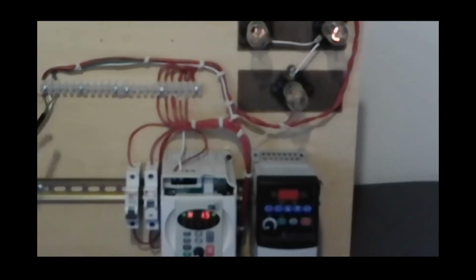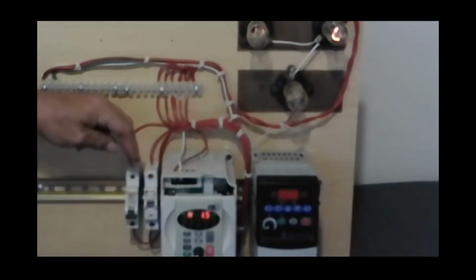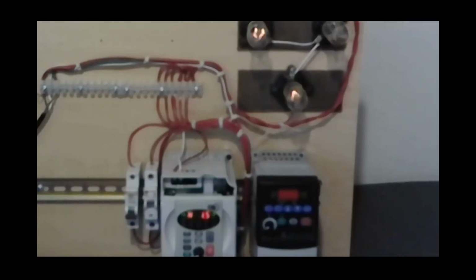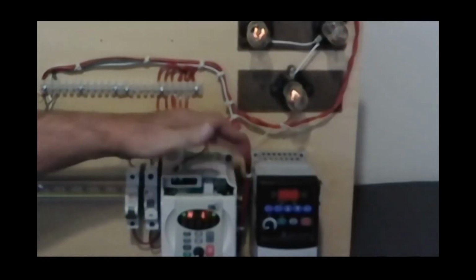You have also problems with the transient voltages coming into these drives. But another problem that happens with these drives is if you put a drive in an area that's got a large magnetic field. So if I put a large circuit breaker right next to this, a three-phase breaker, as that power from that circuit breaker flows through there, the magnetic fields will build up around the breaker and it will induce a voltage on the electronics. This is why many cabinets are going to have metal plates between the circuit breakers and the drives, the circuit breakers and the PLCs. That is an induction shield that prevents magnetic induction from creating voltages.